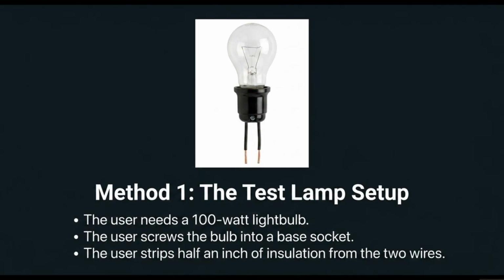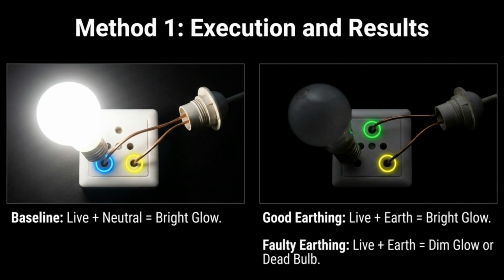For our first method, you will need a 100-watt light bulb, a base socket, and a short length of wire with the insulation stripped from the ends. In this test, a baseline connection between live and neutral should produce a bright glow. Testing between live and earth should also show a bright glow. A dim or dead bulb indicates faulty earth.